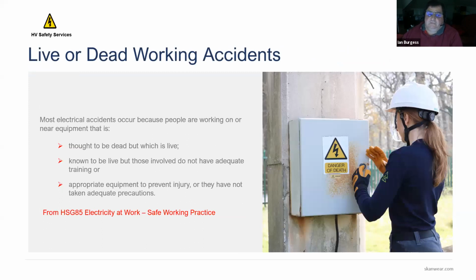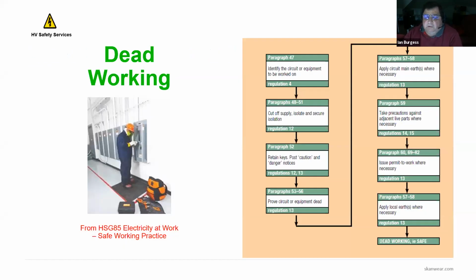So live and dead accidents are generally caused by people who think it's dead but it's actually live, or who know it's live but don't take adequate precautions, or don't have adequate training to do the work, or appropriate equipment to prevent injury has not been used. You can see this comes from HSG 85, Electricity at Work. This is a shot from dead working, from HSG 85 again, and it's a lovely little flow chart that shows you a way to get a safe system of work, from identifying the circuit, establishing isolation, proving it dead, down to issuing documents.